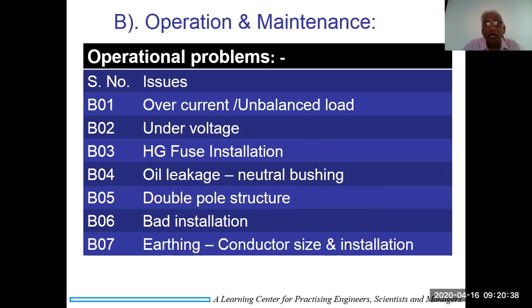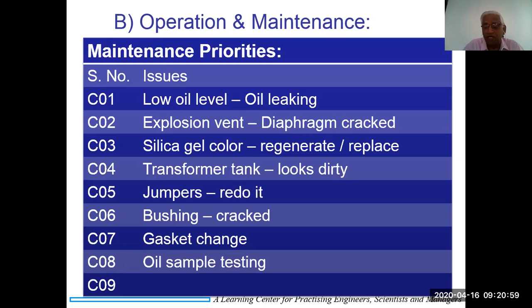Low oil level, oil leakage, explosion vent, diaphragm cracked, silica gel color, regenerate and replace, transformer tank looks dirty, jumper redo it, bushing cracked, gasket change is required, oil sampling testing. Maintenance management: update specifications meeting the requirements, selection testing at site, commissioning, outsourcing repair, selection, capability, periodic supervision, quality assurance and warranty, oil filtration, contamination, training, skills development, dedication, review of the best practices.